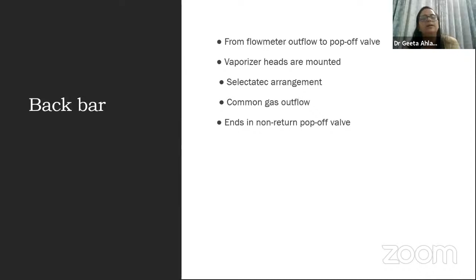Vaporizers, as we know, are as varied and available to us as the makes of machines are. Most of the machines are specific. They have their specific vaporizers, and in institutes which purchase different kinds of machines, a variety of vaporizers are available. They have their own key fills and are specific to different machines. So don't just assume, okay, I have this vaporizer and I can use it. You should always ensure whether it matches and can be mounted onto your machine, that the filling apparatus you have is compatible with that vaporizer and is actually functioning. It is an important part of the checking that you ensure it can be mounted.